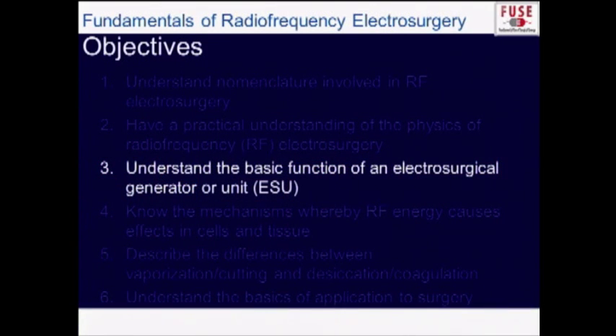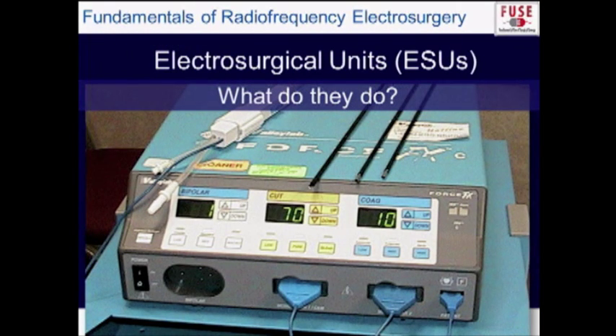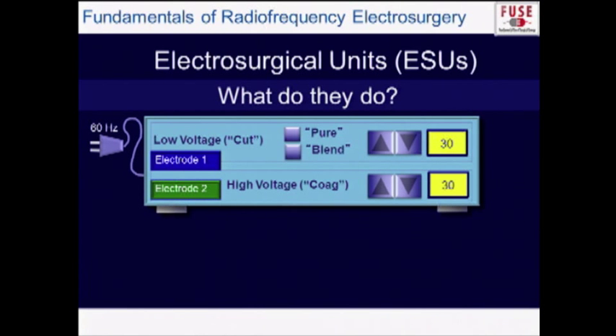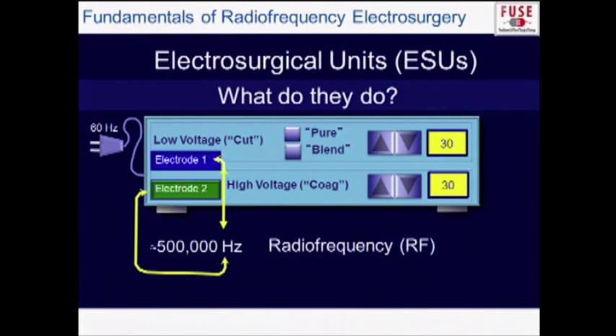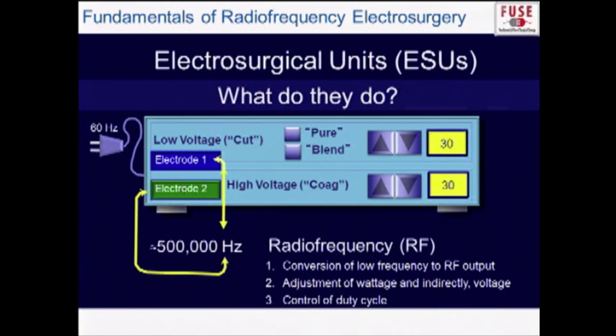Electrosurgical generators take the 60 Hz, 60-cycle-per-second alternating current from the wall and convert it to one that's 500,000 cycles per second — or approximately 500 kHz. That's why it's called radiofrequency: 570 on the AM dial corresponds to 570 kHz. Generators also allow you to adjust voltage and wattage, control the duty cycle, and more advanced devices go even further.